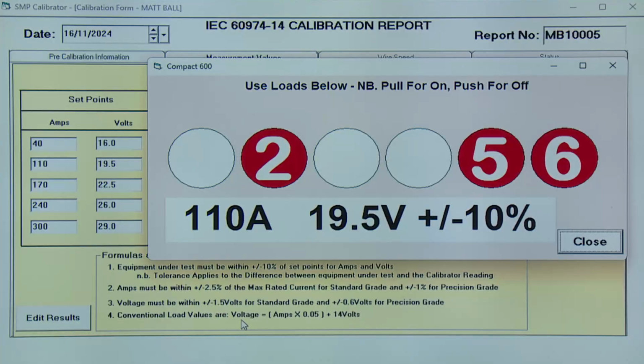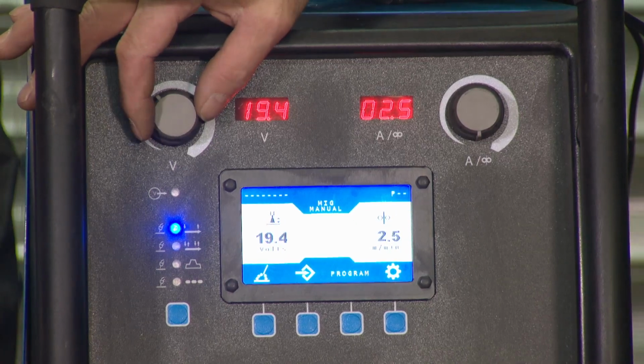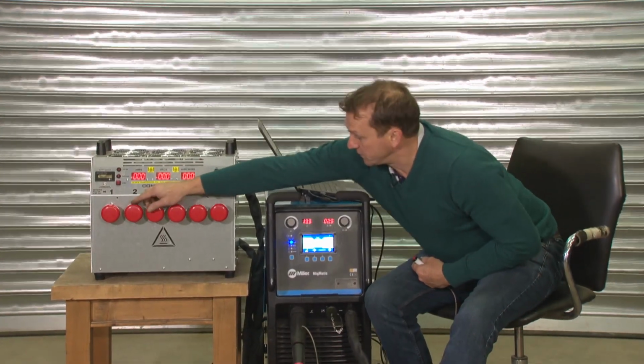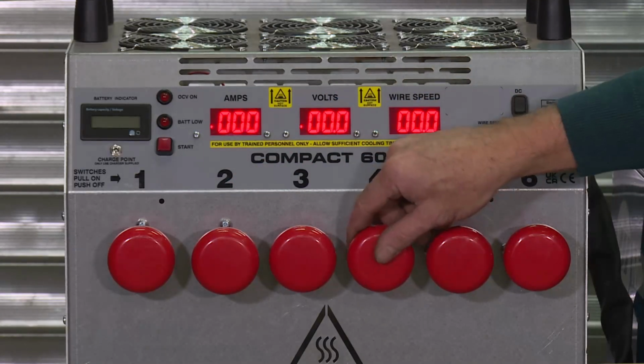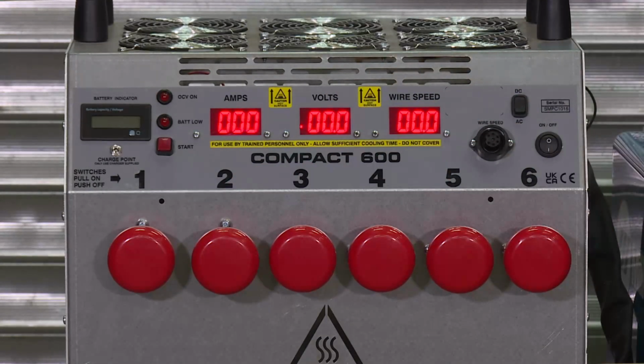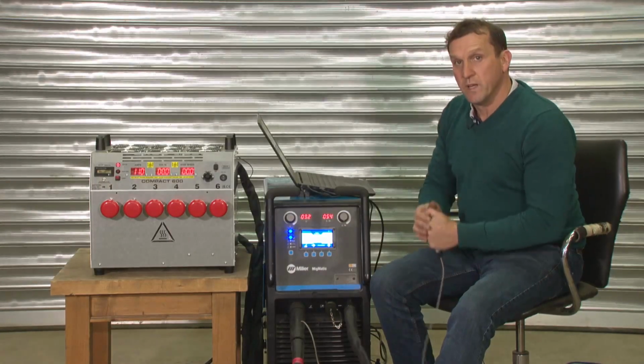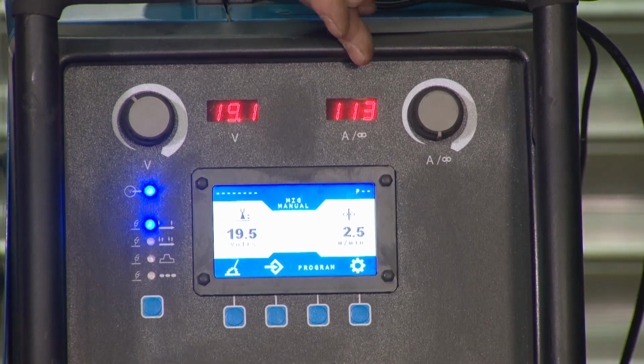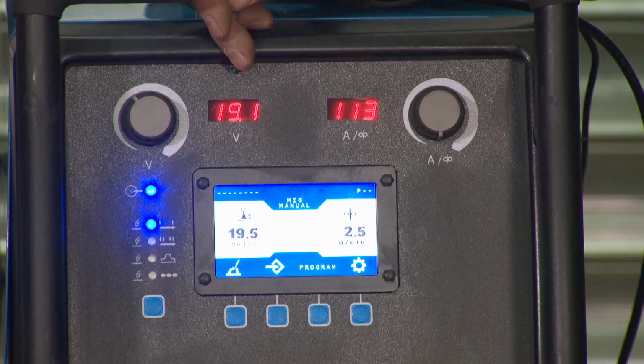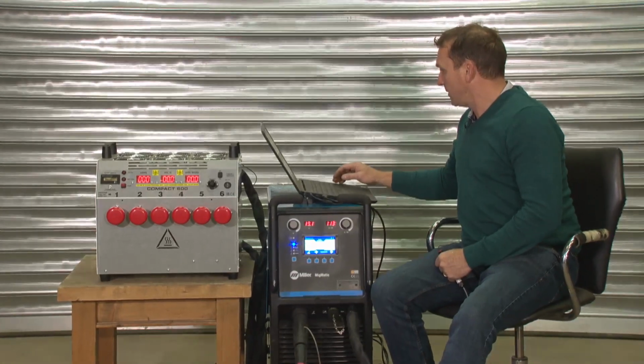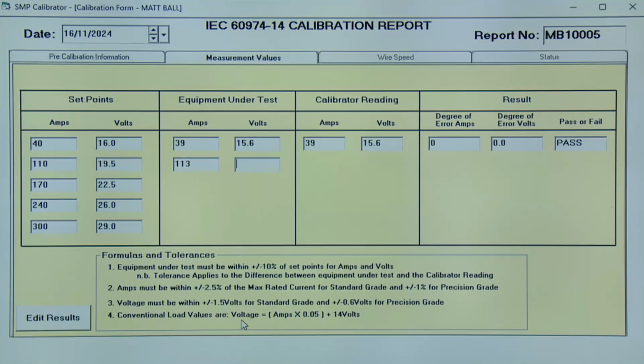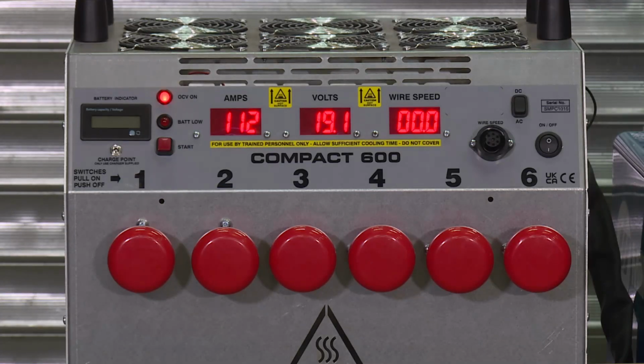On to the next reading, we need to select 19.5 volts and load switches 2, 5 and 6. We then energize. We have 113 amps and 19.1 volts. Then we take the calibrator reading, 112 and 19.1 volts.